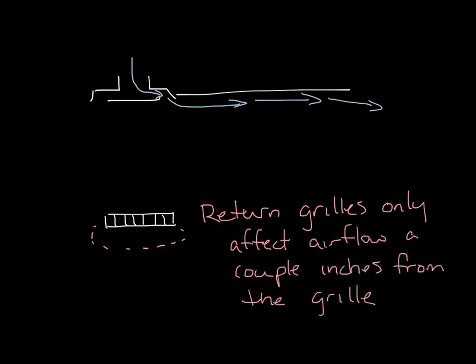So if you don't want to take my word for it the ASHRAE Handbook HVAC Applications Chapter 57 Room Air Distribution says that return grill location is far less critical than with outlets. In fact room air intake affects room air motion only immediately around the grill.